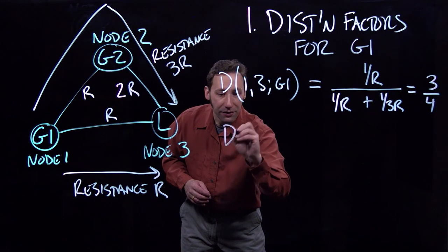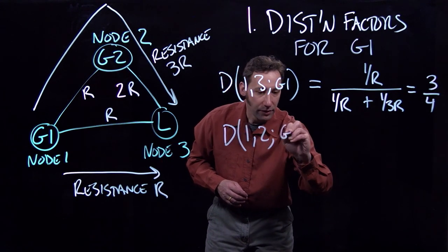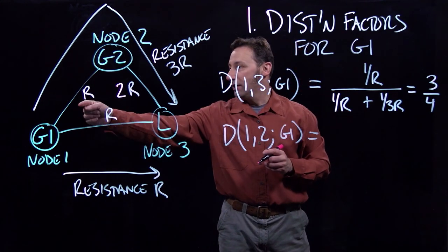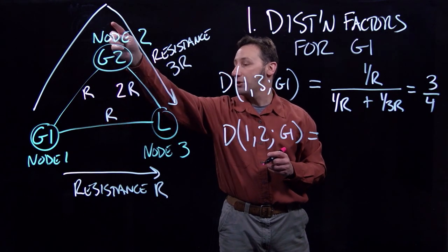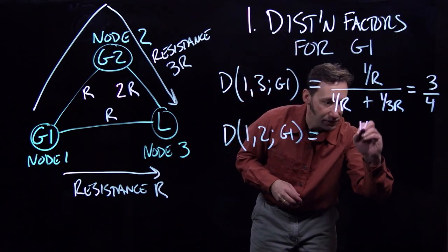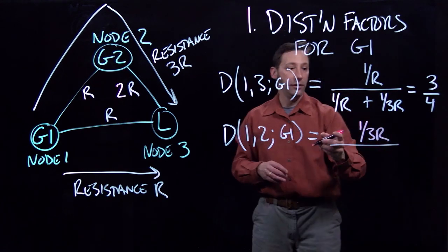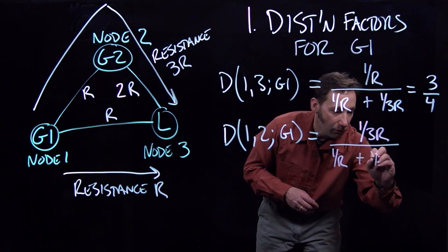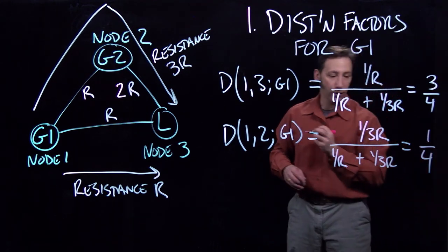Now we're going to calculate the distribution factor on line 1 to 2 from G1. The numerator is going to be the inverse of the total resistance of the long path that goes from node 1 to node 2 to node 3, which is 3R — so the inverse of that is 1 over 3R. In the denominator, we have 1 over R plus 1 over 3R, and we're going to get 1 fourth.